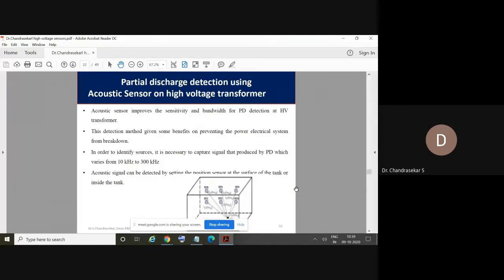So how are these acoustic sensors used for high voltage transformers? Why are we going for acoustic sensors in high voltage transformers? Because, as I already told, the transformer is of very large size and completely filled with oil, so if there is any fault in a particular place inside the tank, it is very difficult to locate. Using a high frequency current transformer, which we already discussed, if you get a PD signal, we can tell that some PD activity or leakage current is happening inside the transformer. Whereas, to accurately locate the fault, in which winding, there are so many primary and secondary windings consisting of so many turns, in which portion of the winding the fault is occurring, if you want to pinpoint the exact fault location, then we need to go for such acoustic based sensors.